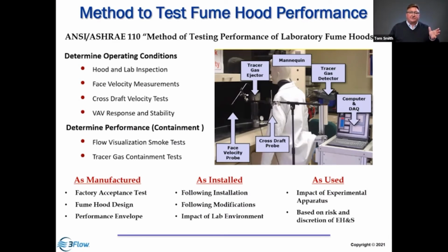Just because it has exhaust flow, these other factors could influence the containment. The conditions in the lab, the total flow, the pressurization, these are all important elements that can influence the containment of the hood. So the as-installed commissioning test should be the very last thing that's done to certify the hood after the labs have been tested and balanced and they've been commissioned, saying all the parts and pieces are working properly, it's working as we expected.